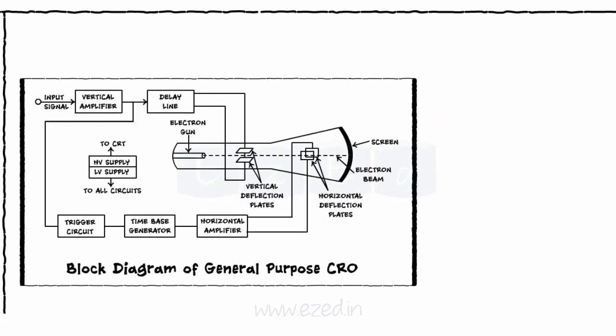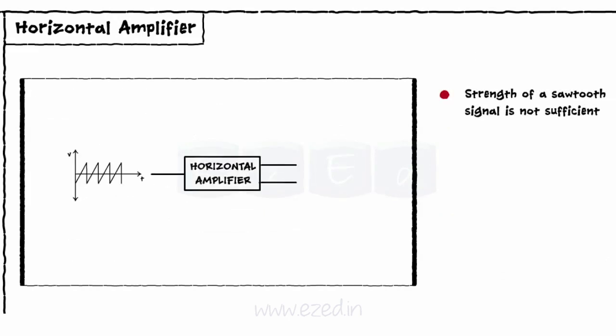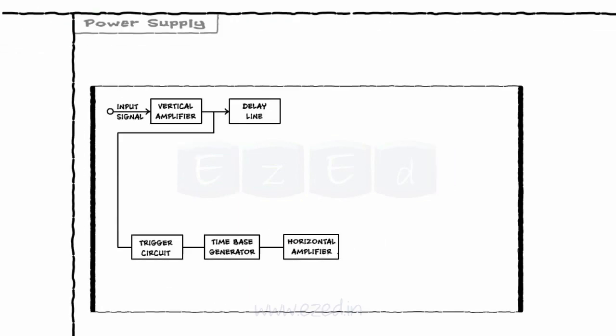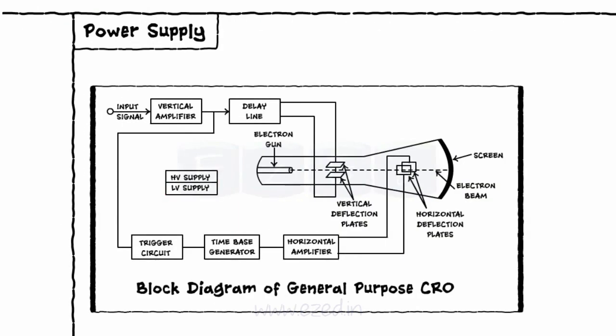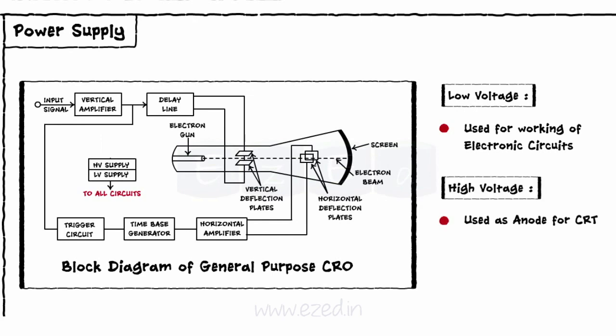The last block is a horizontal amplifier. The strength of the sawtooth signal available at the output of the time base generator is not sufficient. Thus, before applying it to the horizontal plates, the signal is amplified using a horizontal amplifier. Every instrument needs a power supply for it to work. The power supply section of a CRO generates two levels of DC voltage. A low voltage is used for the working of electronic circuits and a high voltage level is used as the anode for CRT. The high voltage generated is of the order of 1000 to 1500 volts.